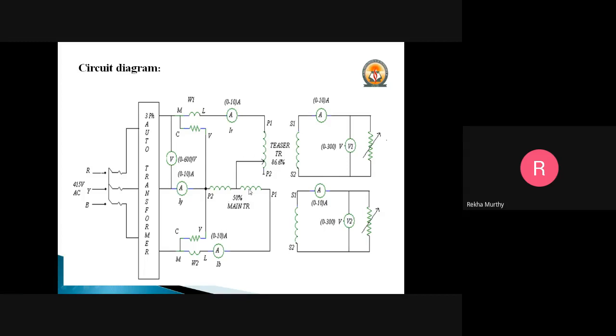Now, how to do the remaining connections? It is very simple. From one end, we connect the second part of the connection, going with the teaser transformer. The first end of this should be given to the ammeter, which will always be in series, preferring 0 to 10 amperes. The other end of the ammeter needs to be connected to L, and MC should be shorted, with M, which is main, connected to one end of the supply, that is the 3-phase.